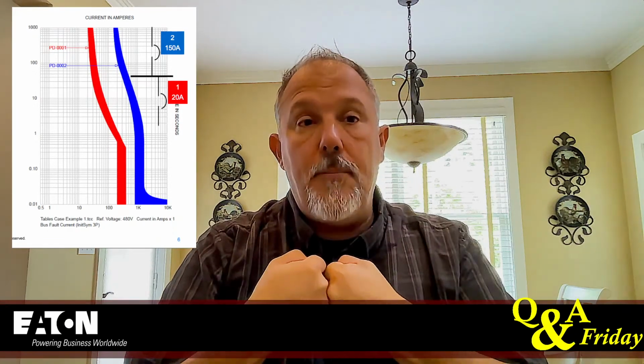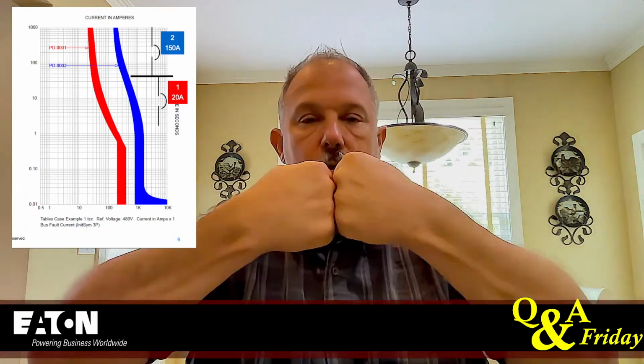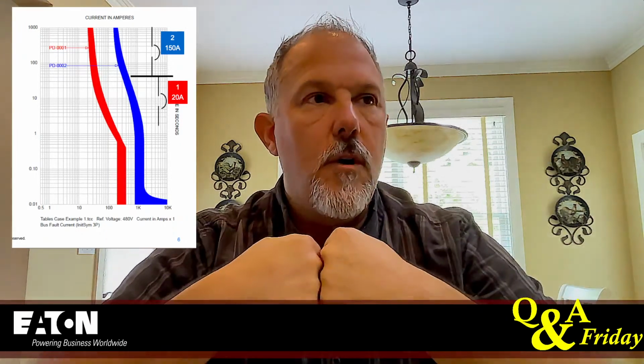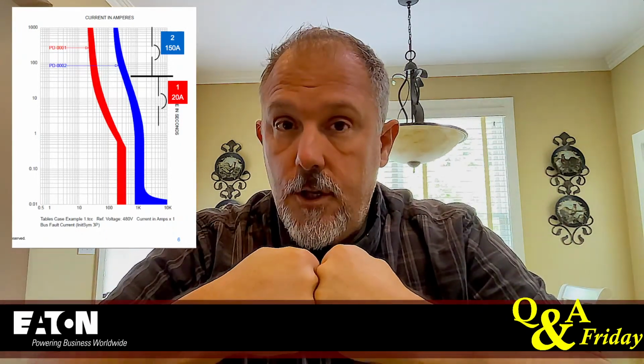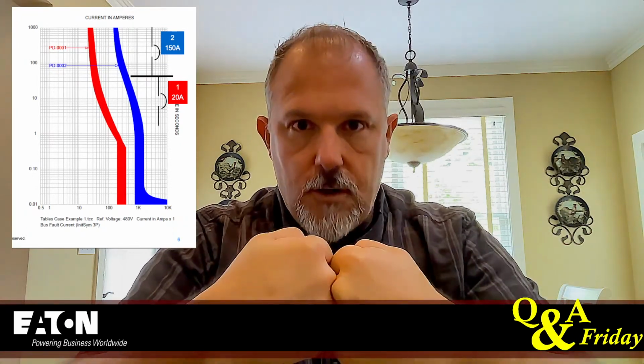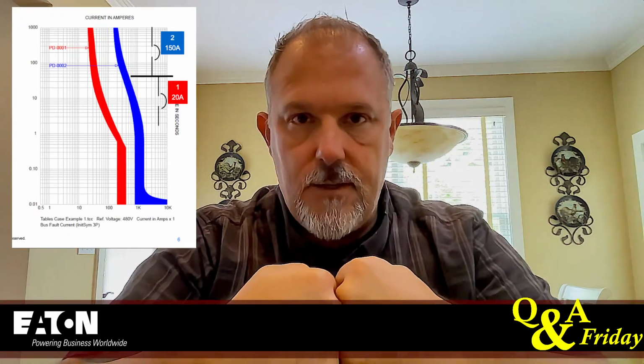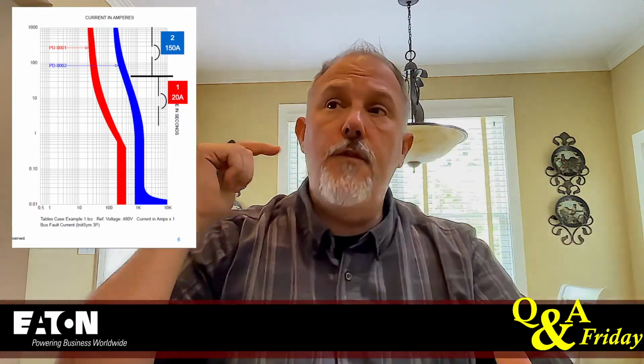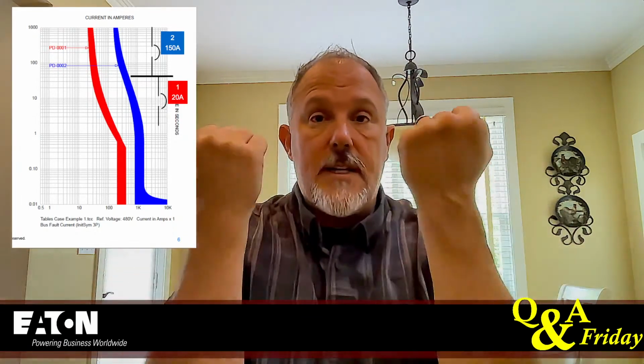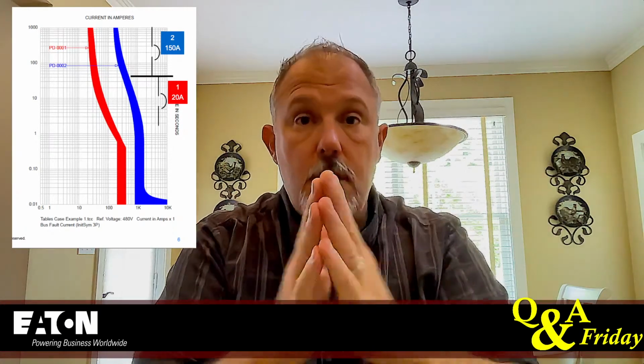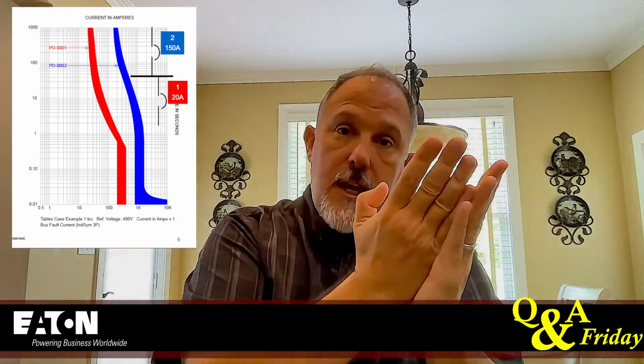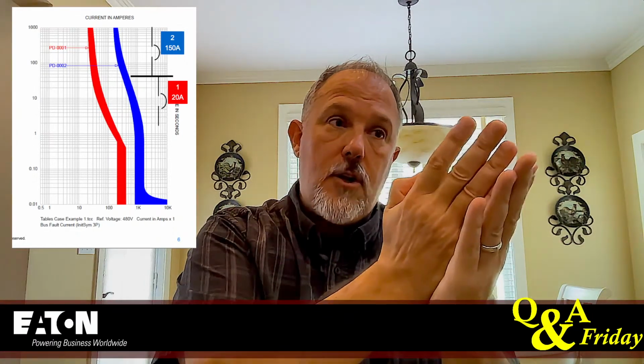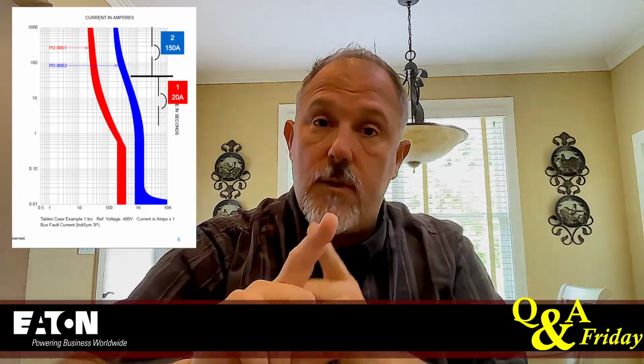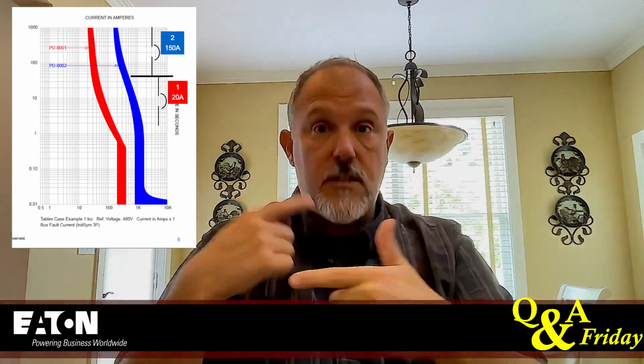And I can do that by putting a beefier device whenever you want a circuit breaker to put pressure on a set of contacts for high fault currents. You want enough pressure on those contacts. How do I get pressure on a contact? Think about a circuit breaker. What's inside of a circuit breaker? You've got springs, you've got a set of contacts, you've got contact surfaces, you've got metal that's pushing a lever down to hold the contacts together. And during fault conditions, what's the other thing you've got going on? You've got flux, you've got magnetic forces that want to push those contacts apart.